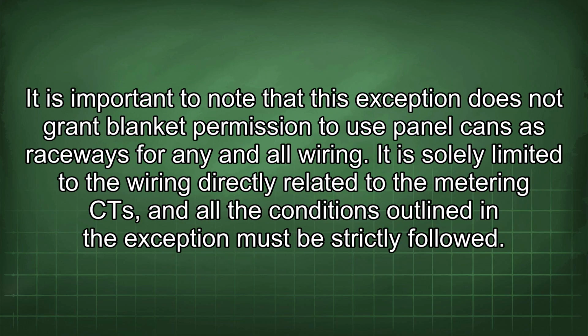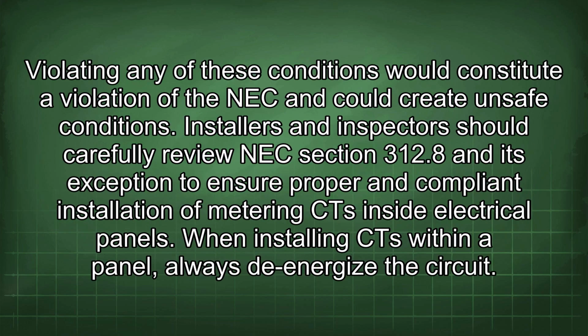It is important to note that this exception does not grant blanket permission to use panel cans as raceways for any and all wiring. It is solely limited to the wiring directly related to the metering CT, and all the conditions outlined in the exception must be strictly followed. Violating any of these conditions would constitute a violation of the NEC and could create unsafe conditions.